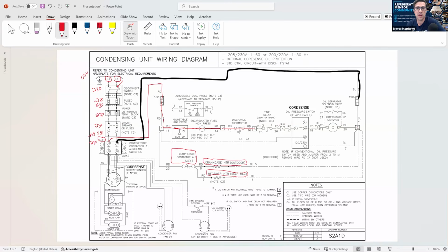And then if there's a time delay, a delay on break, it all depends if there's a time delay, because in some systems, like this must be an anti-short cycle timer, most likely. So if the compressor starts up and it shuts down, it has to wait 2 to 3 minutes. I'll have to double check that in the manual. If power is going through there to terminal 4, then we got a CoreSense module in here.